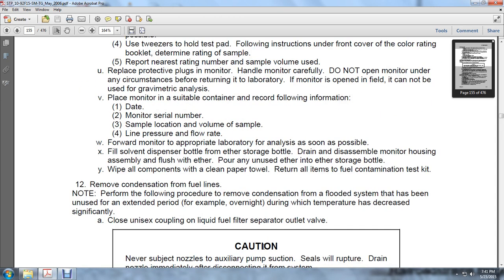12. Removing the condensation from fuel lines. Perform the following procedure to remove condensation from a flooded system that has been unused for an extended period, for example overnight, during which the temperature has decreased significantly. Close the unisex coupling on the liquid fuel filter separator outlet valve.